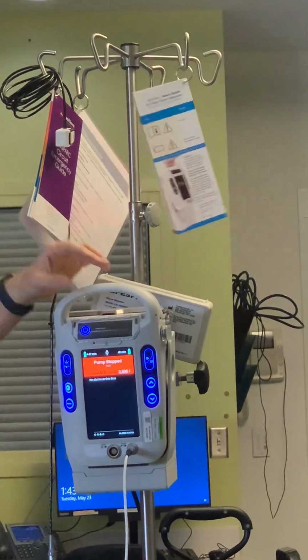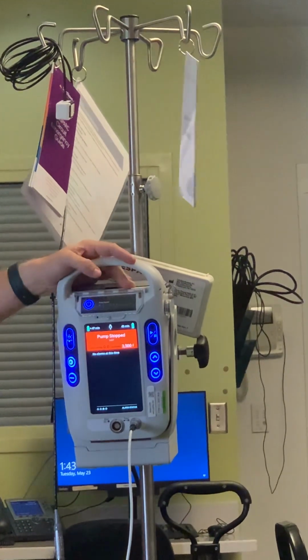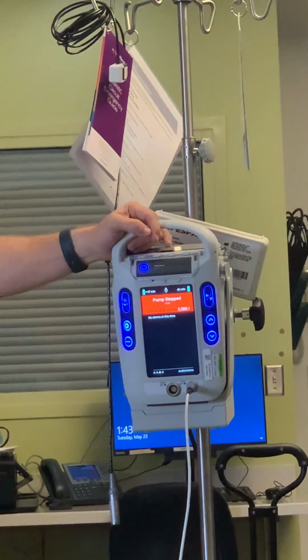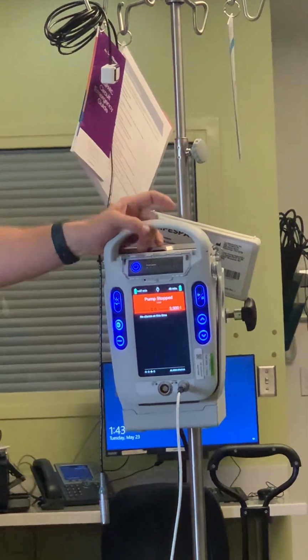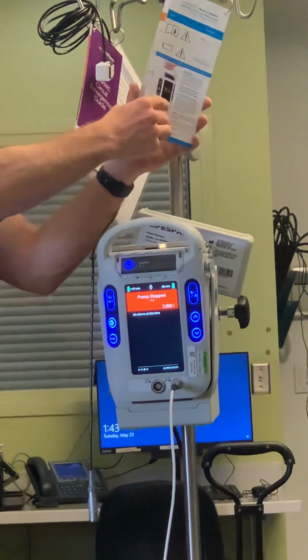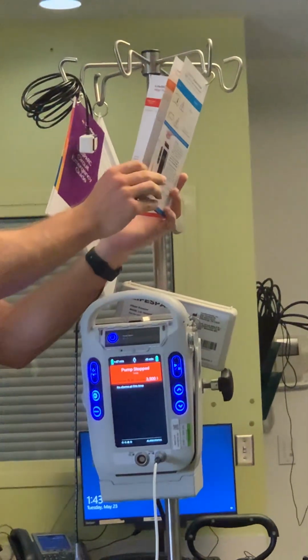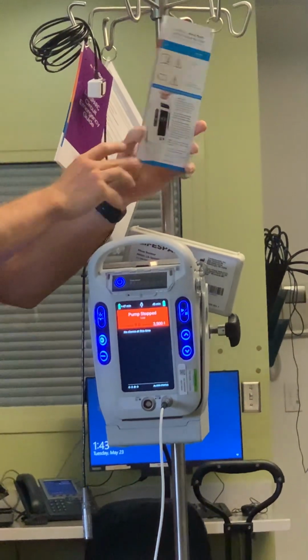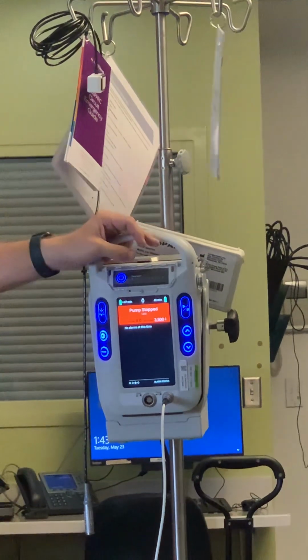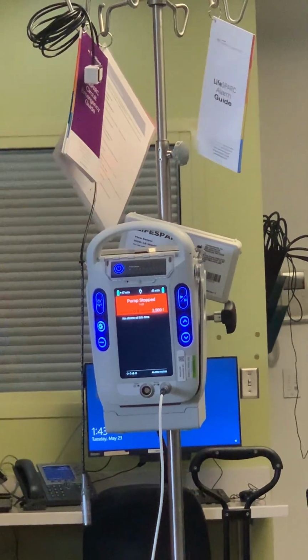3 of the critical alarms are battery related, so if you always keep it plugged in, you'll never see those. So if one battery gets low, if both batteries get low, or if there's no batteries and you're not on power, or if the pump stops, then it's gonna start letting you know it's not happy.